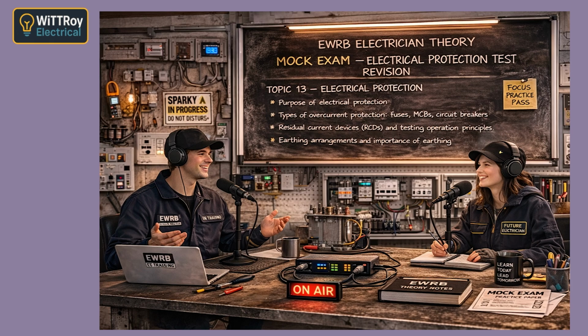If I only remember one sentence, I can still choose the wrong answer. That's exactly right. Protection questions are often about sequence and consequence. For example, imbalance causes RCD tripping, low impedance increases fault current, poor earthing weakens fault clearing, and incorrect device choice affects safety. So the exam is checking whether I understand what happens next. Yes, that is why cause and effect matters so much in protection. This helped a lot more than just hearing the correct option. Good, that's the point. Once you understand the chain, the answers become much clearer.